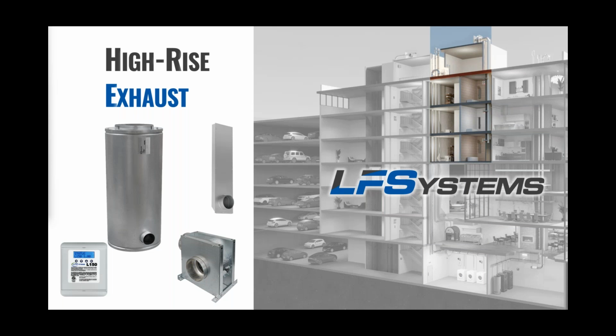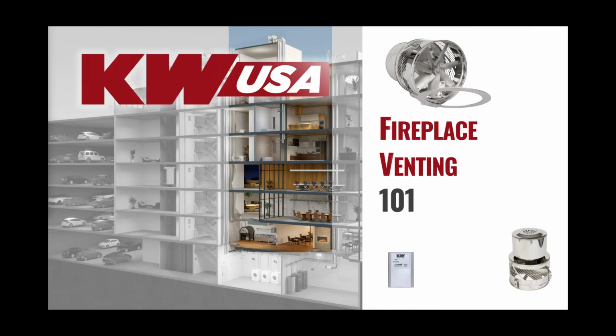High-rise exhaust: if you get into kitchen, bath, or laundry for multi-family, multi-story, we can do the shaft, the subducts, the fans, and the controls, all pressure-based. It's a huge energy savings. If you're looking for green technology and high-efficiency operating buildings, that comes less from the electricity and more from makeup air. The less air you're pulling, the less air you need to put back in. Our sister brand, KWUSA, is a partnership with Kutzner & Weber, a German manufacturer for fireplaces, pizza ovens, kilns, coffee roasters, anything weird that you're not sure how to vent. You can contact Buckley and ourselves, and we can help you with that as well.